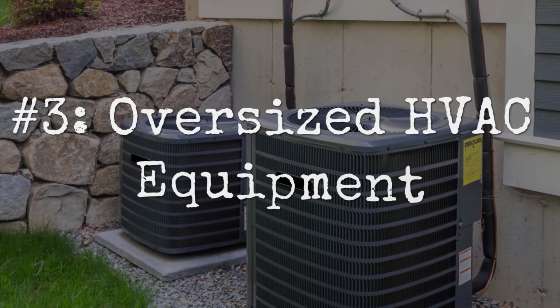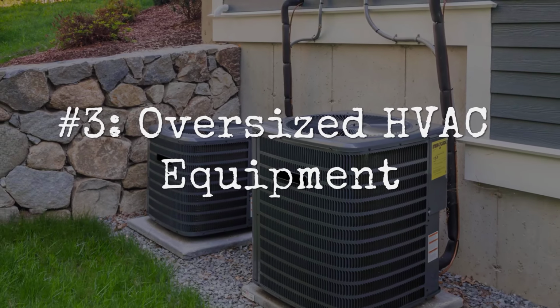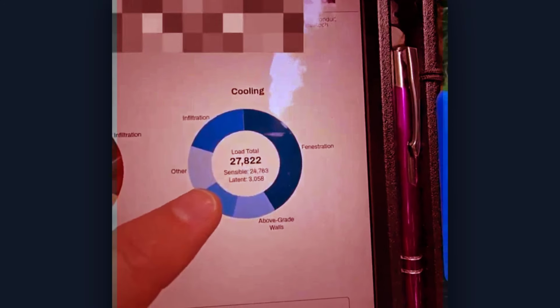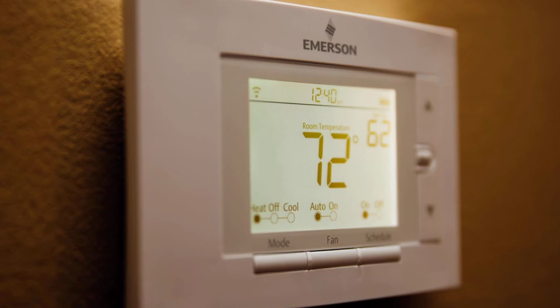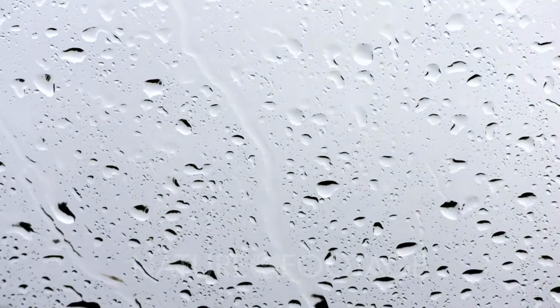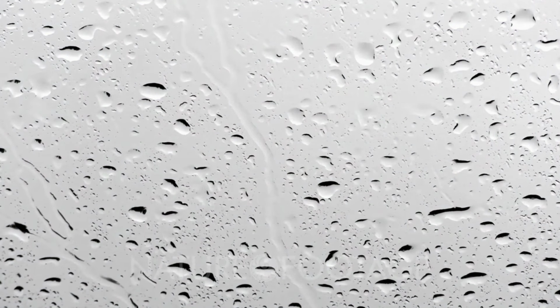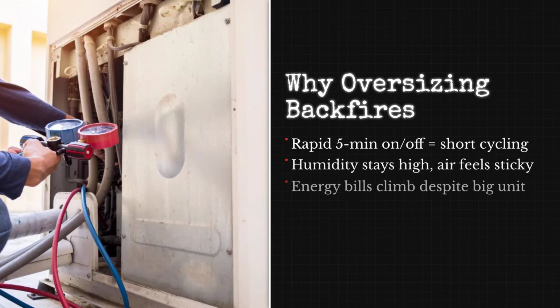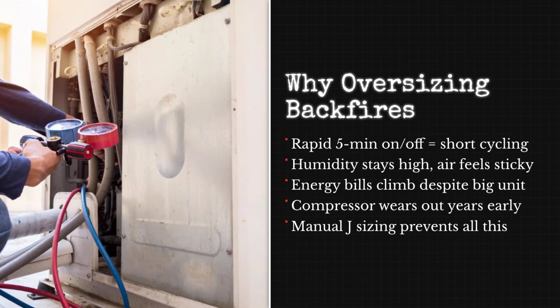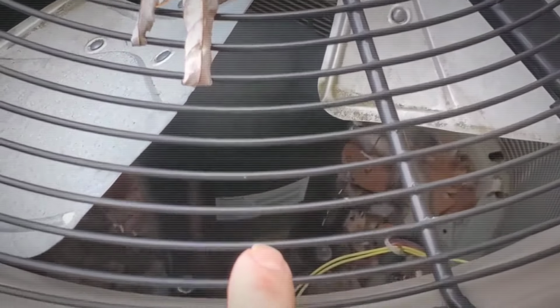Oversized HVAC systems. Sounds backwards? Bigger should mean better cooling, right? But no. In HVAC, oversizing is one of the worst things you can do. An oversized air conditioner cools so fast that the thermostat shuts it off before the system removes humidity. Your house hits 72 degrees but still feels sticky. This is called short cycling, and it causes poor humidity control, premature compressor wear, and wasted energy from repeated startup surges. Why does this happen?